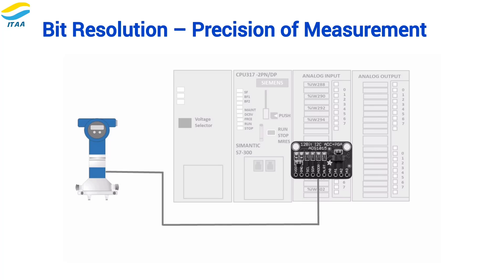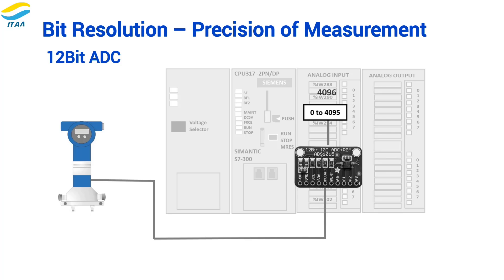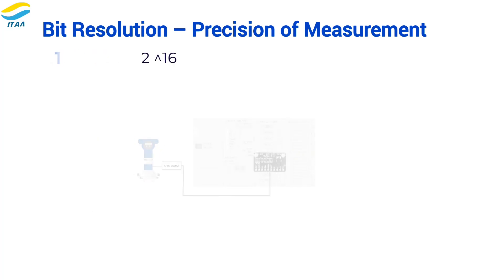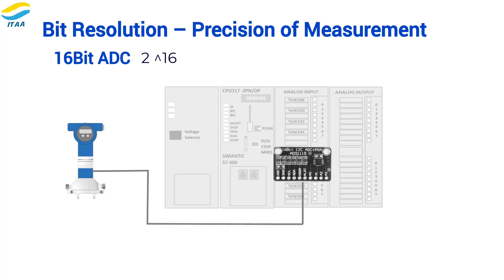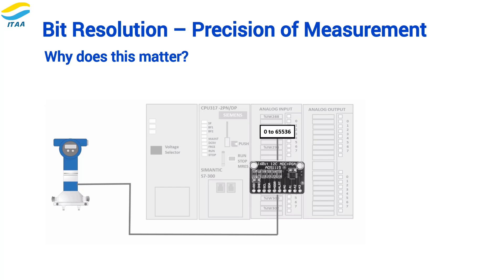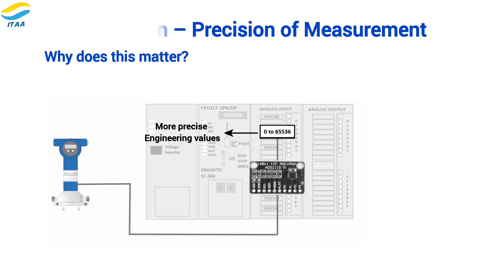Let's talk about bit resolution, which affects how precisely the PLC can measure changes in the tank level. In a 12-bit ADC, we get 4096 possible raw values from 0 to 4095. But with a 16-bit ADC, the range expands to 65,536 counts, enabling even finer measurements. Why does this matter? Higher bit resolution means smaller steps between raw values, so our engineering values become more precise. That increased precision means better control and accuracy in our system.